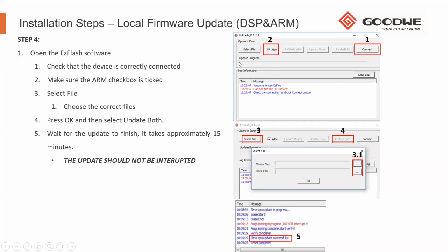We then go through to select file. You'll see there is a master file and a slave file. It is critically important to select the correct master file and the correct slave file. Should you swap these two files around, your inverter will be bricked and it will have to go back for repairs. So unfortunately that will make sure that your inverter doesn't work. It can also lead to the corruption of the control board. So sometimes it will be unrepairable. So it's very important to make sure we select the correct files. Also in our download files, you'll see they will be in separate folders, one called master and one called slave.